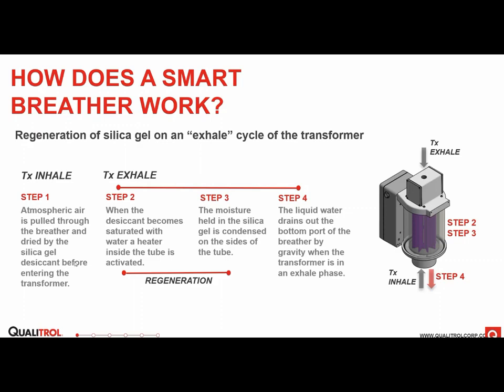entering the transformer. Step two is that during a transformer's exhale cycle, when the desiccant is fully saturated or needs to be regenerated, the regeneration cycle is activated. And the moisture in the silica gel is condensed on the side of the tube and drains out the bottom. And that is the full cycle there. So the smart breather should be able to determine when the exhale phase is and when the best time to regenerate is.